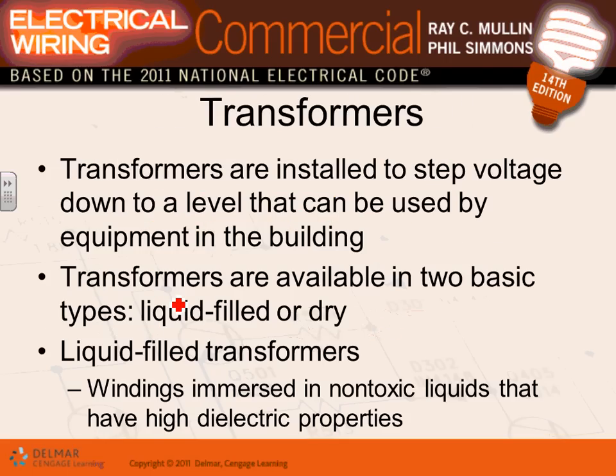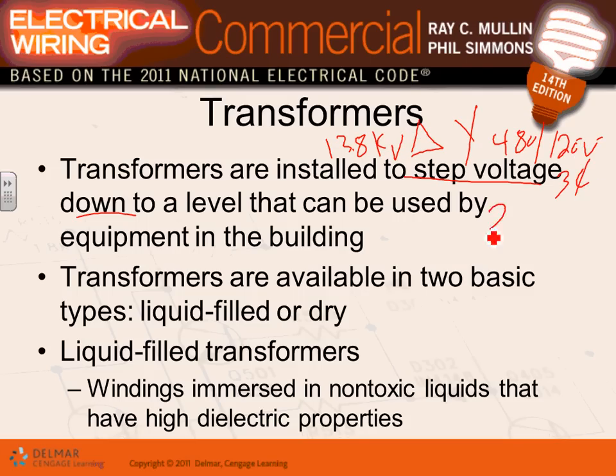So transformers, guys, we use transformers in the building and construction industry typically not to step up the voltage, but to step down the voltage. So we take a voltage at a higher level and step it down to the utilization level. A very good example: typically the service comes to us like this, delta-Y, 13.8 kV here, of course, and this is typically 480/120 volt, three-phase. All these are three-phase, of course, or 208, typically 208/120 volt. These are the typical services that come to a commercial building.